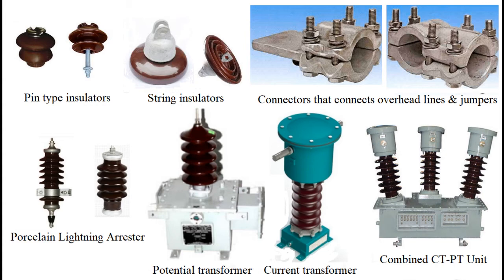Generally, immediately after a pin type insulator, a lightning arrestor is provided for each phase. The purpose of a lightning arrestor is to provide a low resistance path for a lightning stroke. In the absence of a lightning arrestor, the lightning stroke may pass to ground through equipment and consequently damage the equipment. In this way, the lightning arrestor is considered as the protective equipment against lightning stroke.